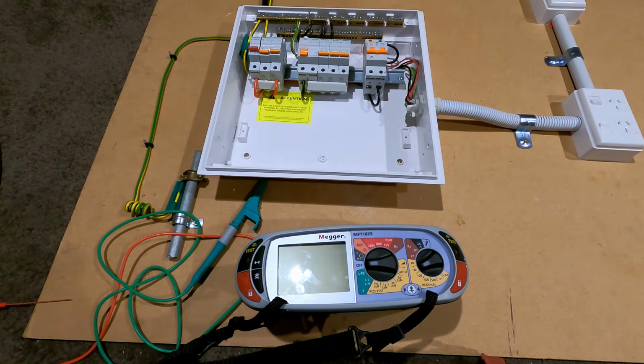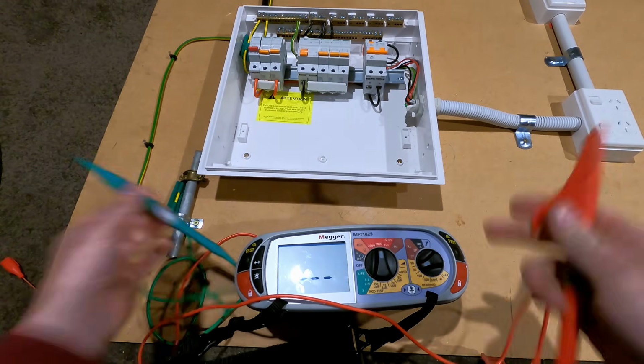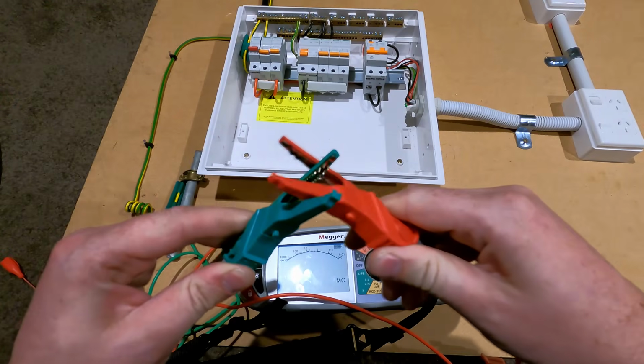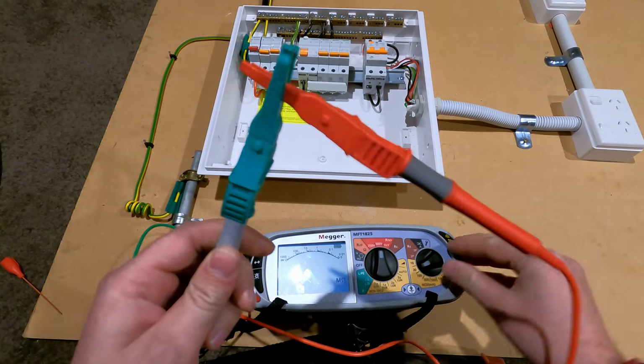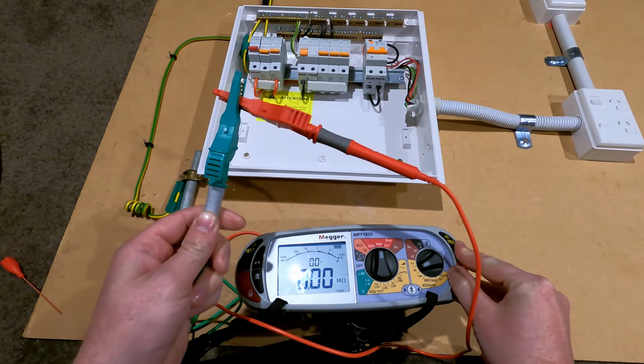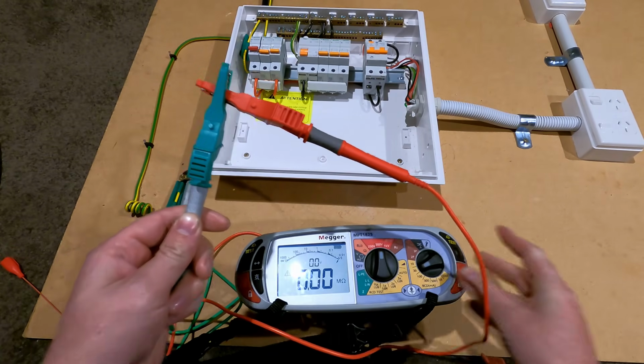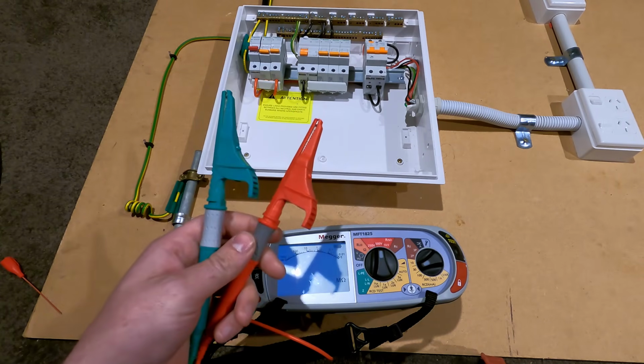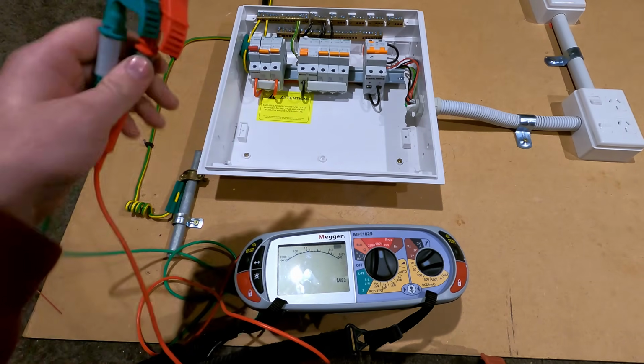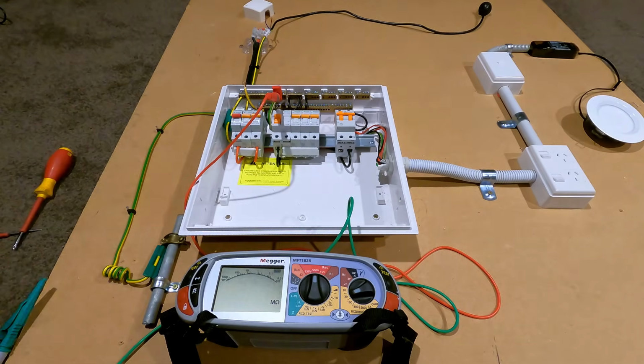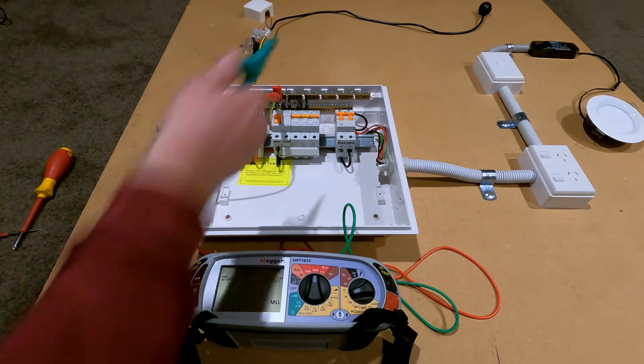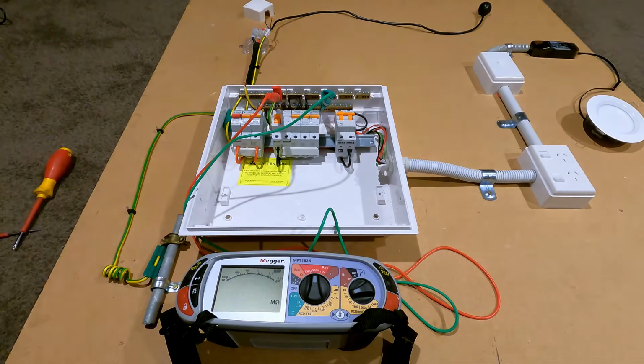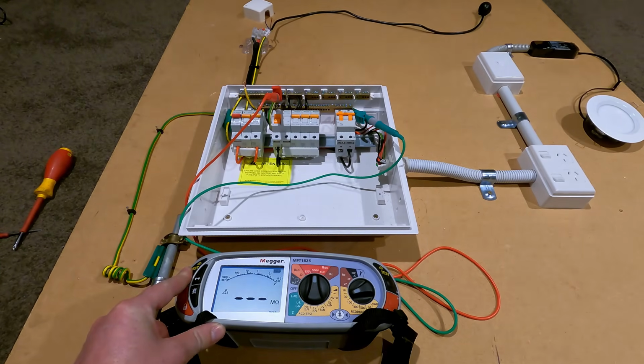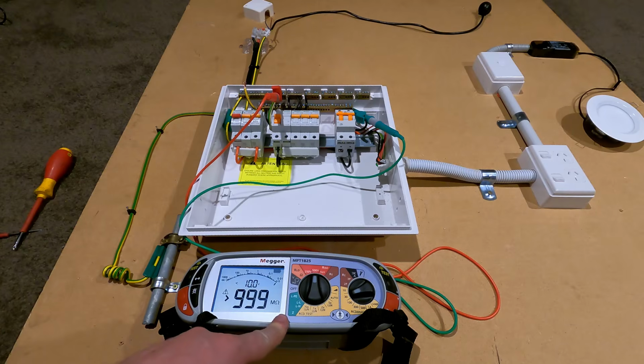Before you start your insulation resistance test, you want to do your first one on the leads of the meter to ensure they're not damaged at all, and you should be able to get a dead short. The result's perfect. Now you've verified these leads are perfectly fine to use to test the installation with. We're going to throw one of these onto the earth bar, the other one onto the neutral bar, and then we're going to hit the test button. And there we have it, greater than 999 mega ohms, which is the result we ideally are looking for.